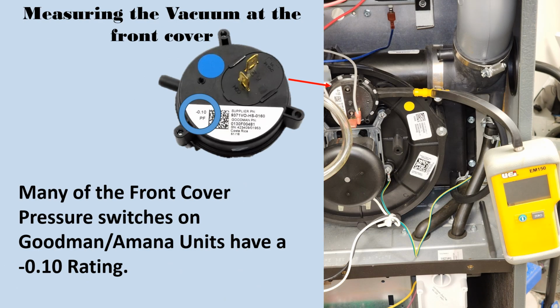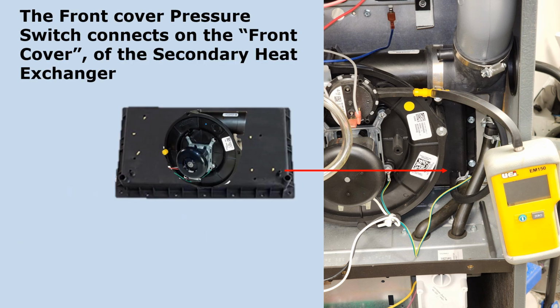Measuring the vacuum at the front cover, if for some reason you wanted to check that, most of the front cover switches, as I said, they're negative 0.10 rated. Front cover pressure switch connects on the front cover of the secondary heat exchanger. And as you see, that little nipple for your manometer, for your pressure switch port, is very close to the drain, to a low corner drain.